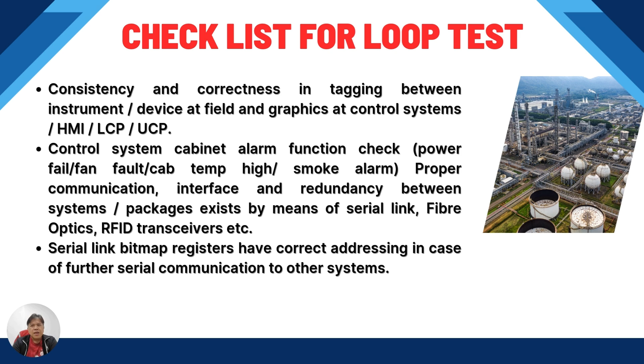So control system cabinets alarm function checks: power, fan failure, temperature high, smoke alarm, proper communication, interface, and redundancy between the system packages and fiber, RFID, etc. So some of the equipment needs redundancy. Okay, so you need to check the serial link, bitmap, registered, correct address, and serial communications to other systems. So if you are in instrument control, maybe you should know those. I mentioned the last part: bitmap, registered, correct address, and serial communications to other systems. All right.